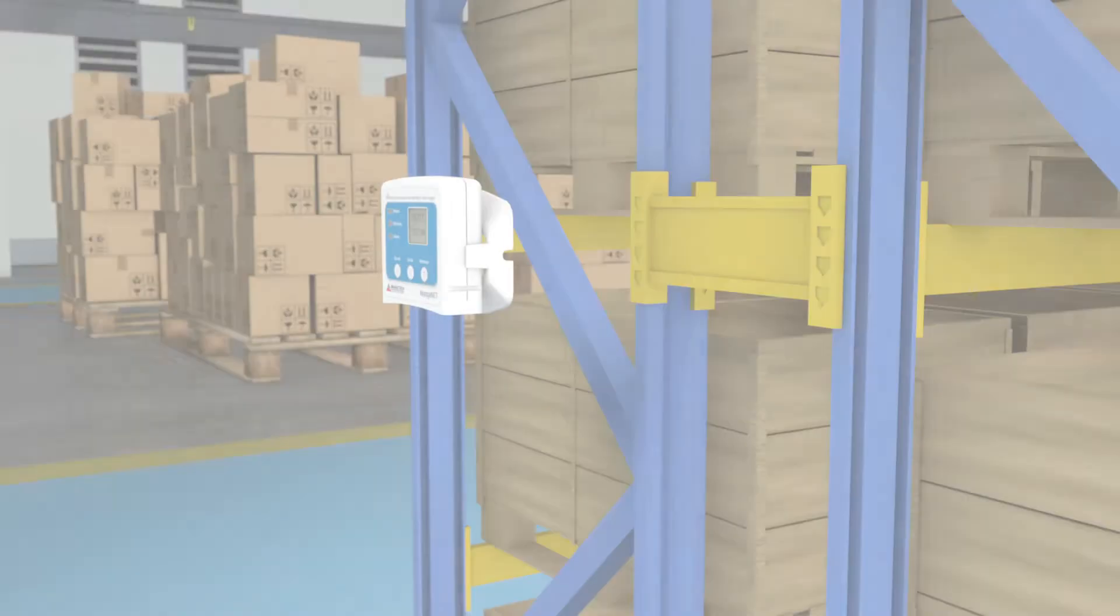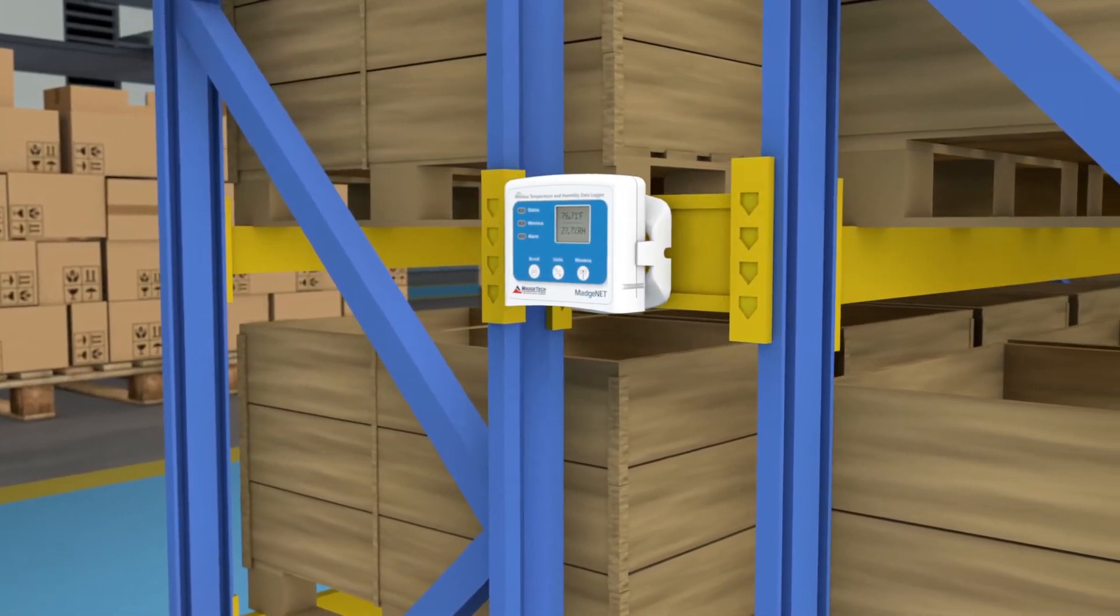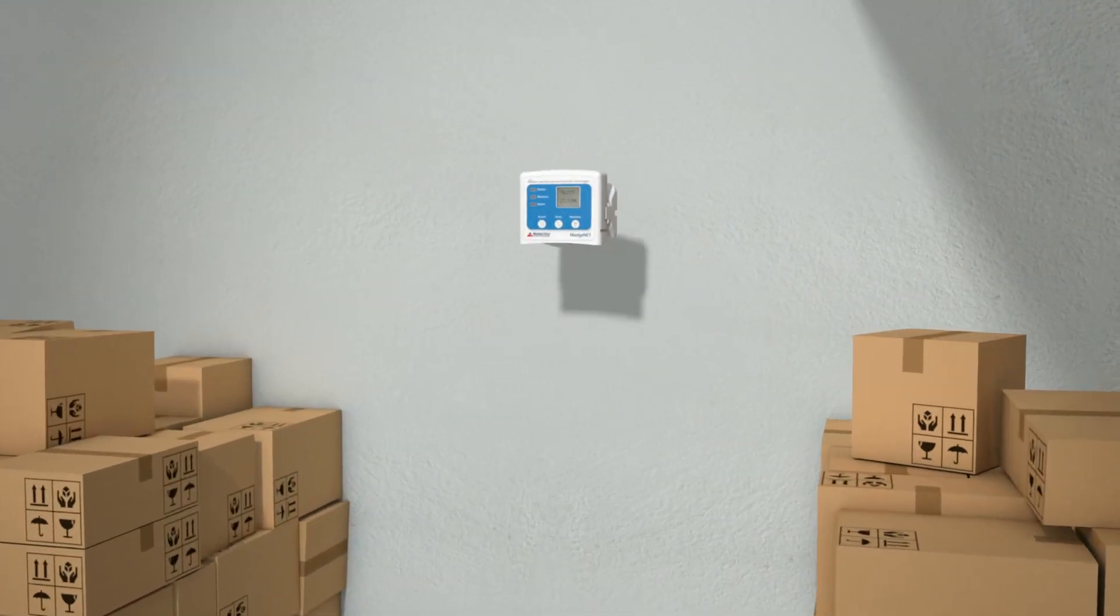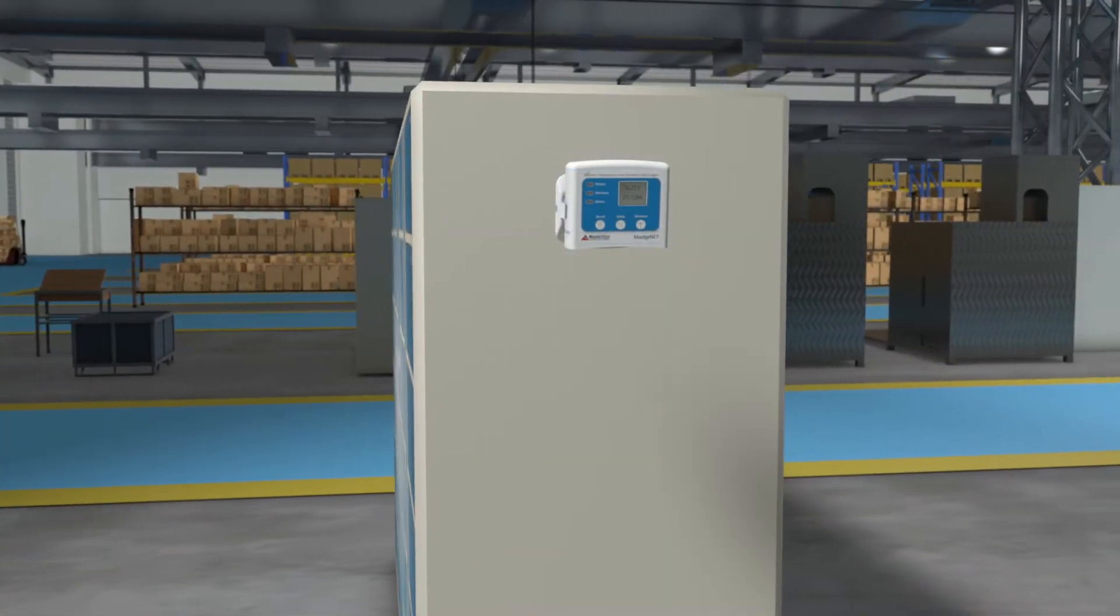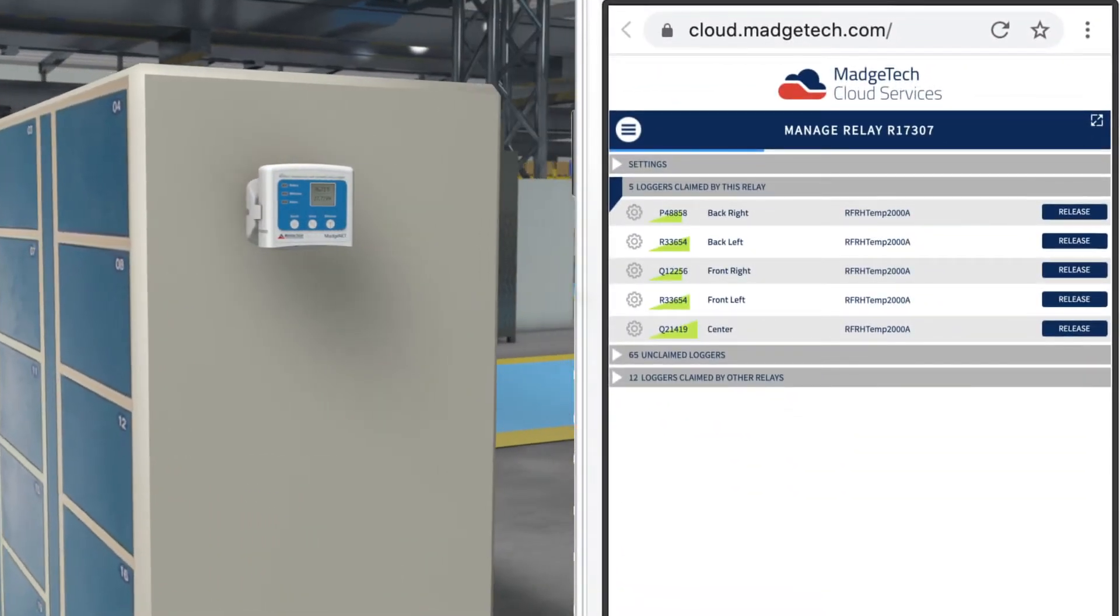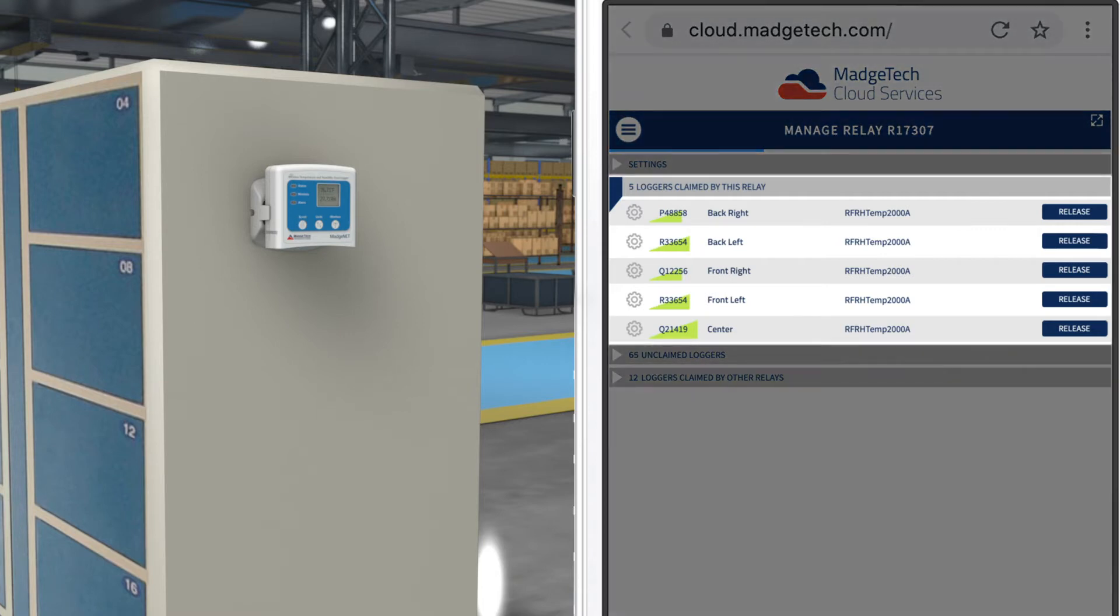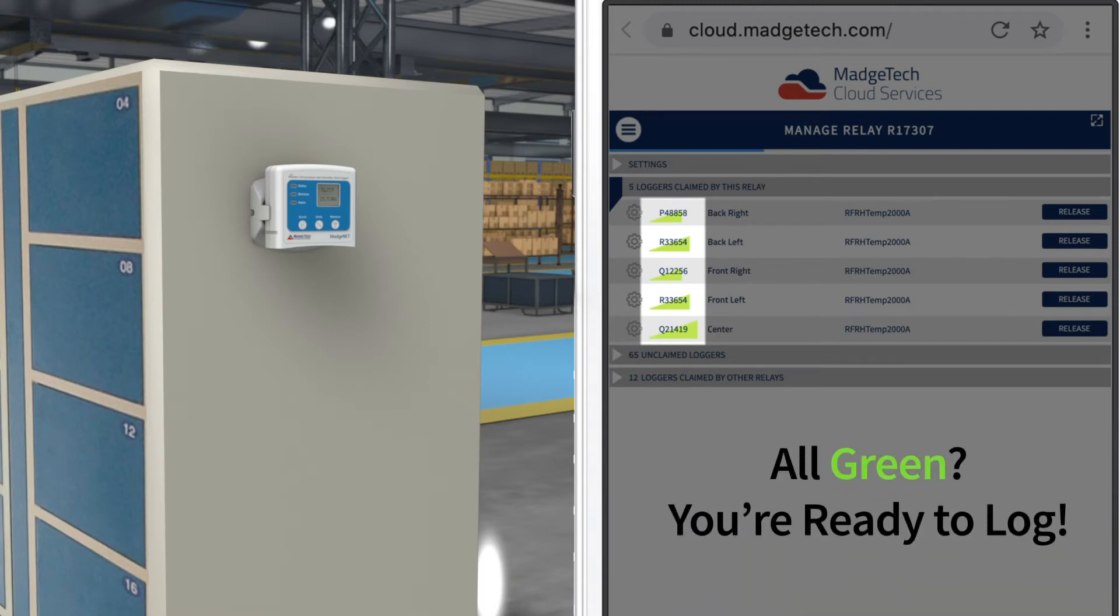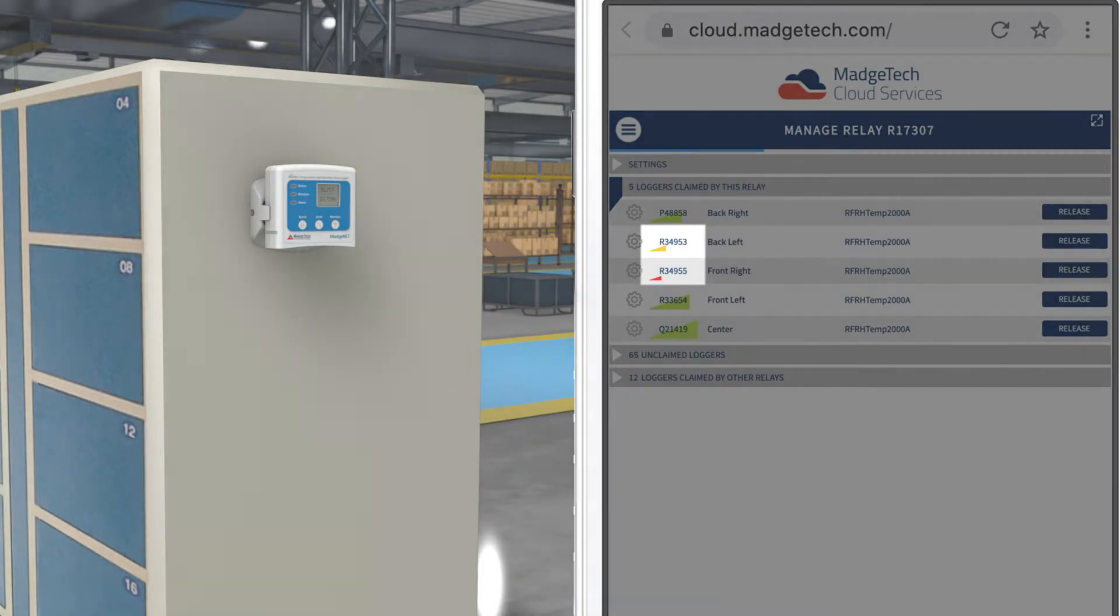Now it's time to deploy the data loggers in the desired critical control point locations. Once all data loggers have been deployed, check the quality of connection between the devices on the network. To do this, once again reference the Manage Relays page within the MadgeTech cloud web application. Within this page, expand the list for loggers claimed by this relay. Here, a signal strength indicator will be shown for each device. If all signal strength indicators are green, the network is complete. If any loggers indicate a poor connection, move on to step 4.